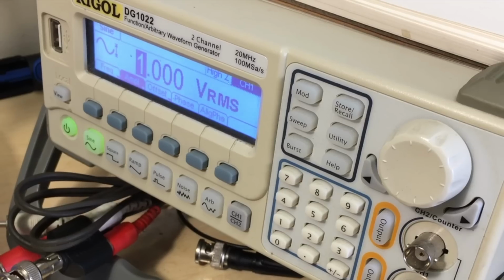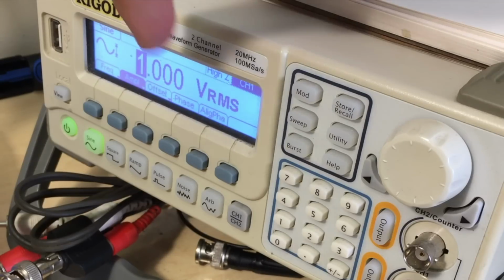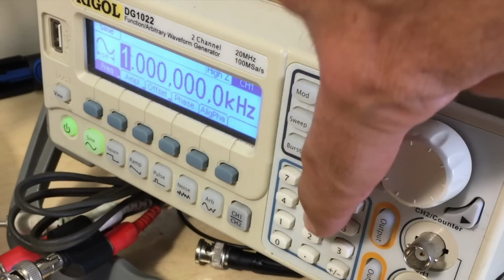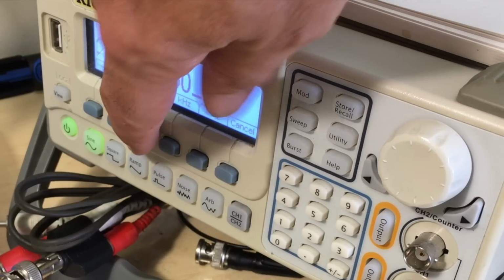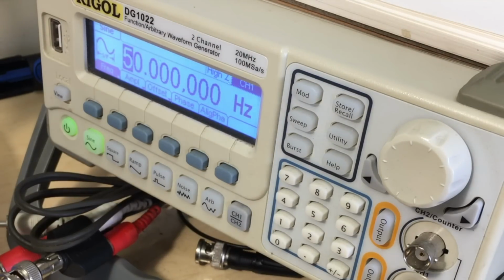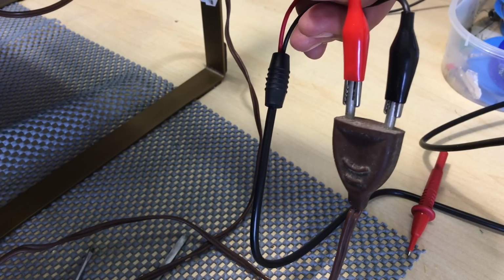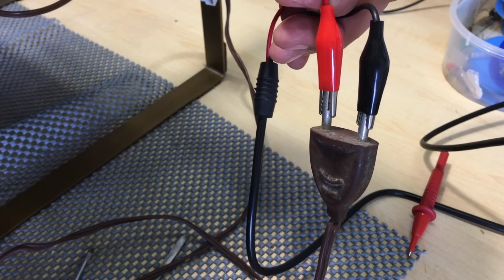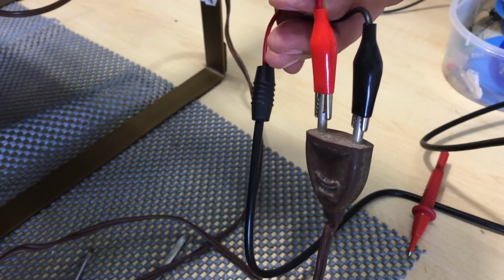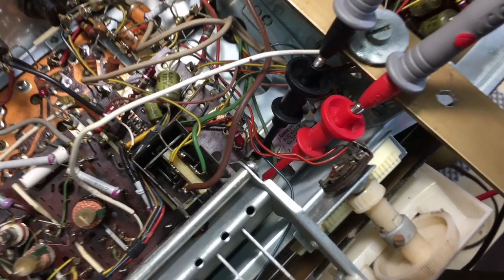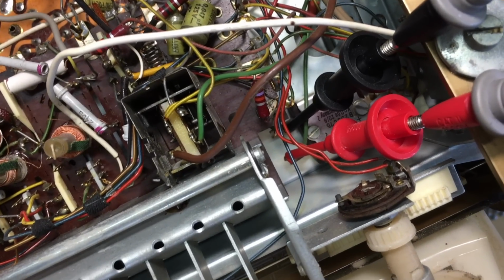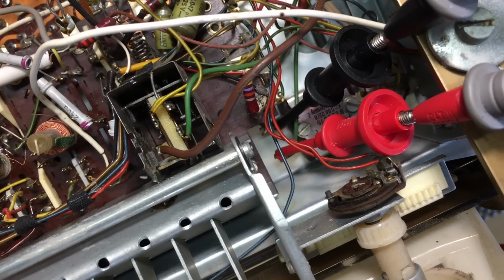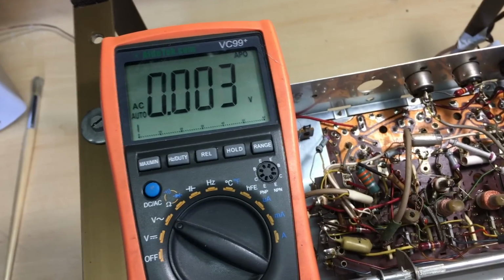Next step, I'm going to give it 1 volt RMS and a 50 hertz signal, basically simulating mains at 1 volt. I'll feed that into the mains plug as if our mains was 1 volt RMS, and see what we get on the secondary. I have the multimeter on AC volts connected to the AC input of the selenium rectifier, the output of the secondary from the transformer, and I measure 0 volts AC.